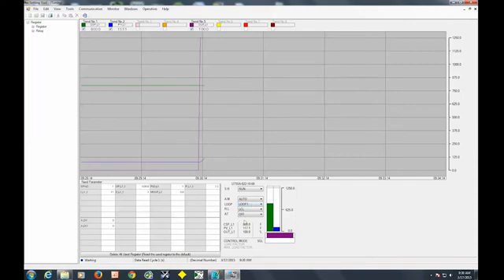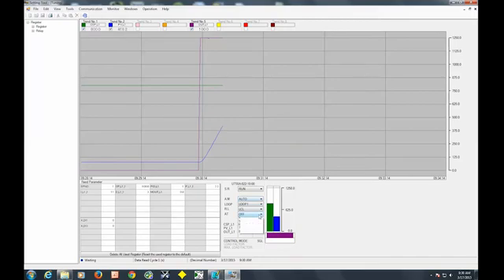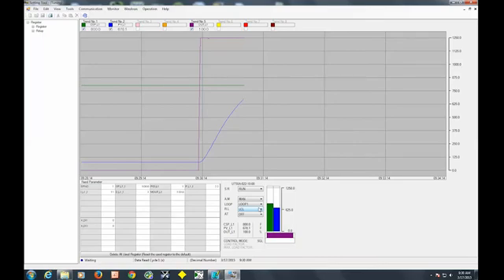Now we can put it in auto-tune. What auto-tune is going to be doing here is going to 100% output. The value is going to go up above the set point slightly. It's going to cut the output back to 0%. You'll see your output drop below the set point slightly. It'll do that cycle three times, make a calculation, and then automatically set your PID settings. The controller will return to normal operation after that. While you're actually auto-tuning, the manual light, the red LED, will flash. When it's done, that light goes out.